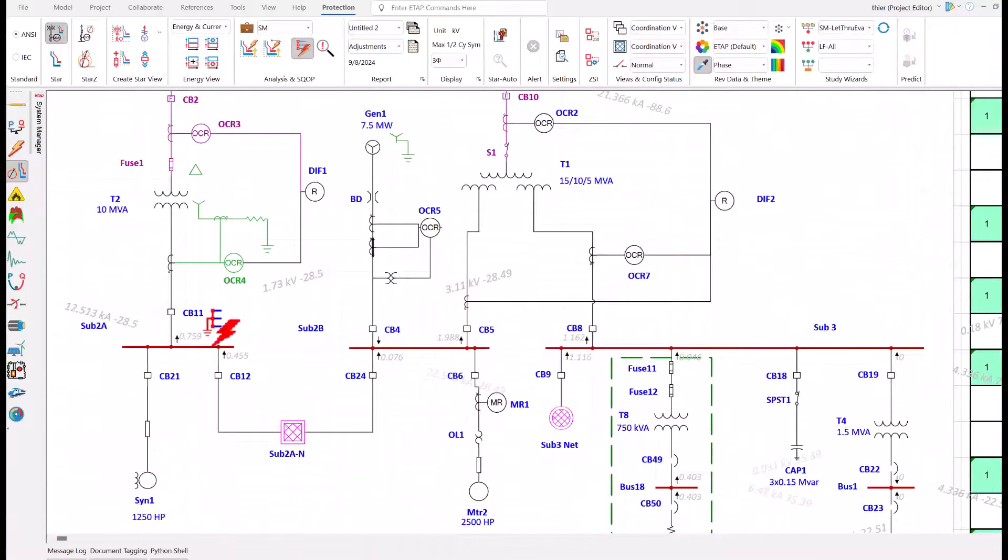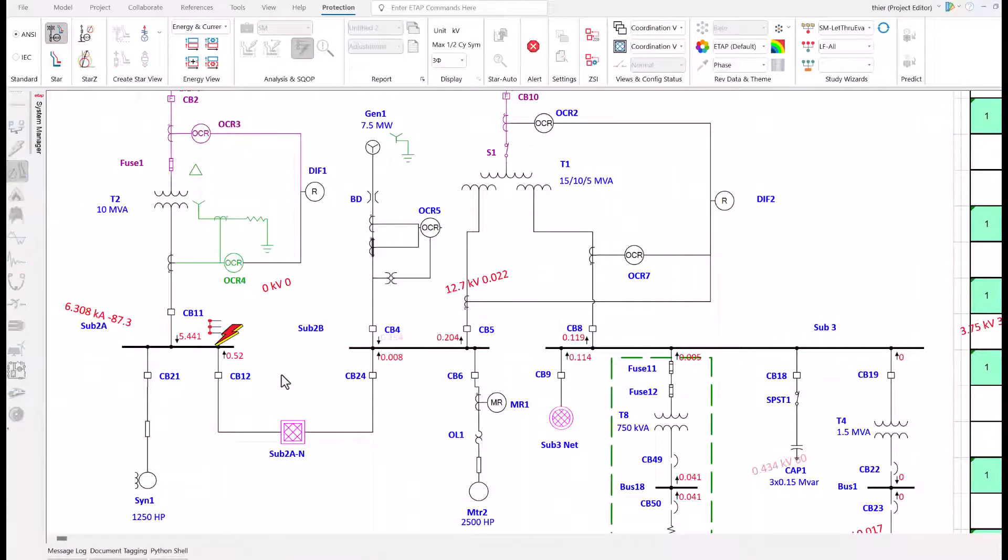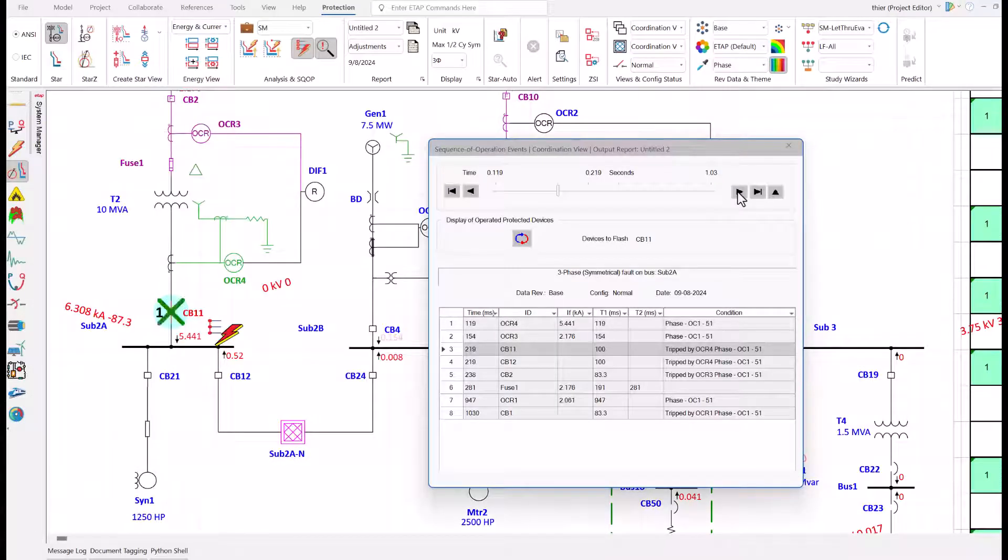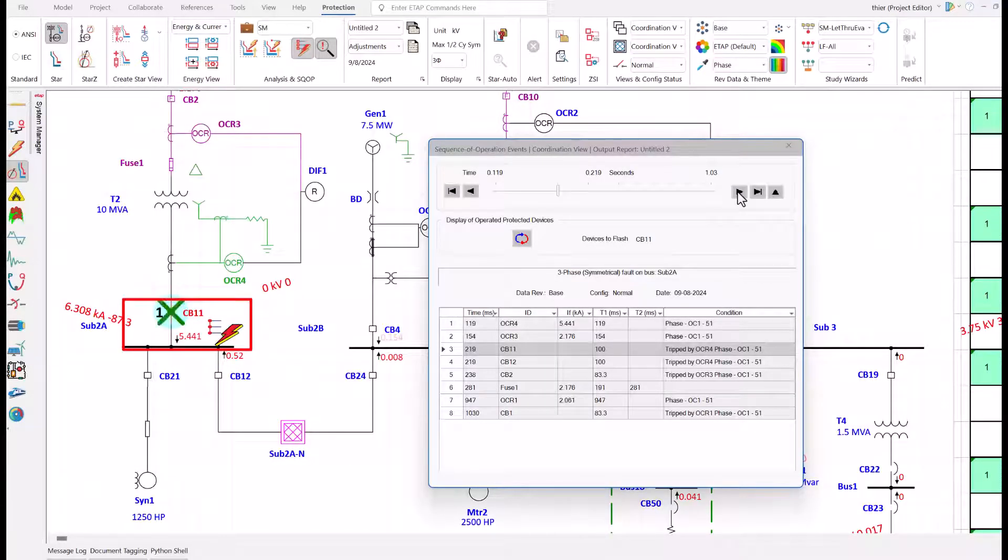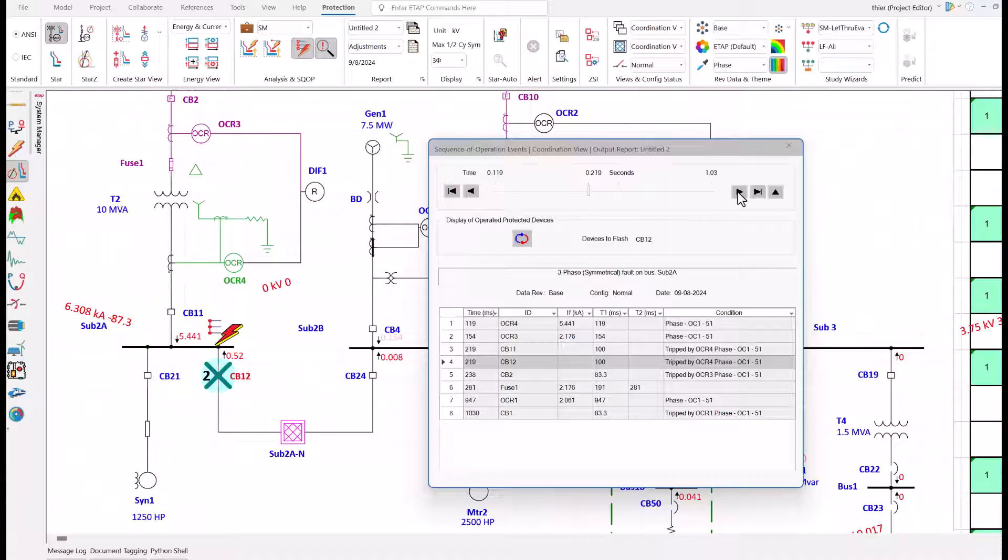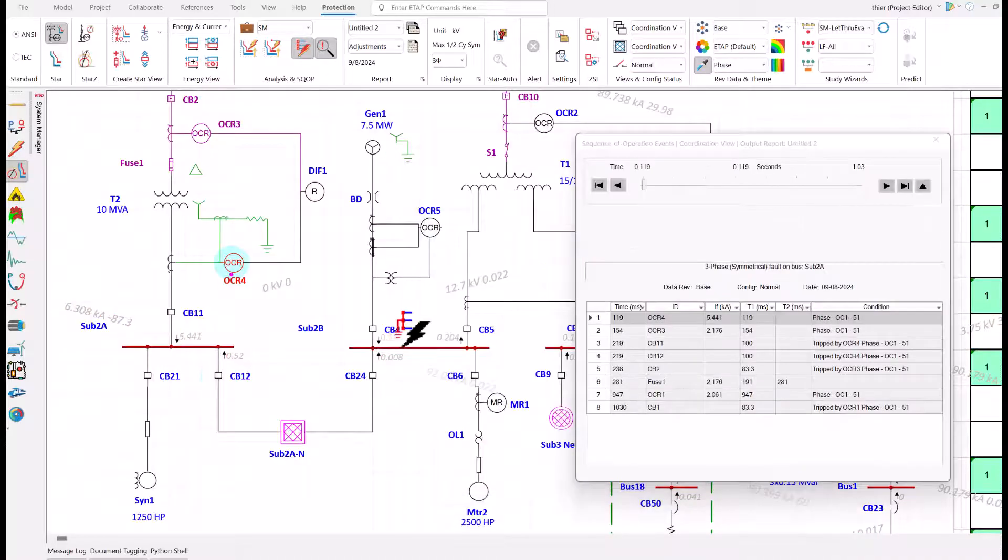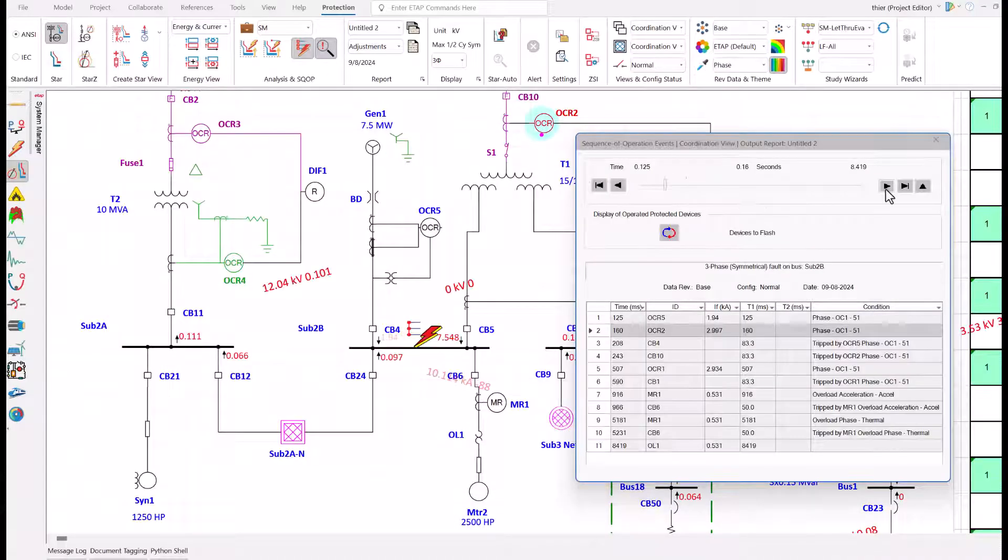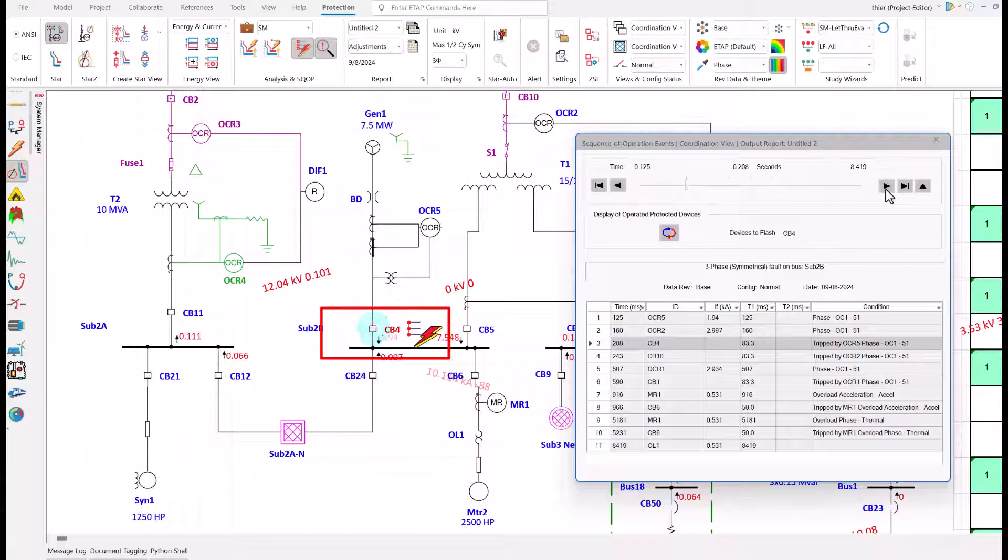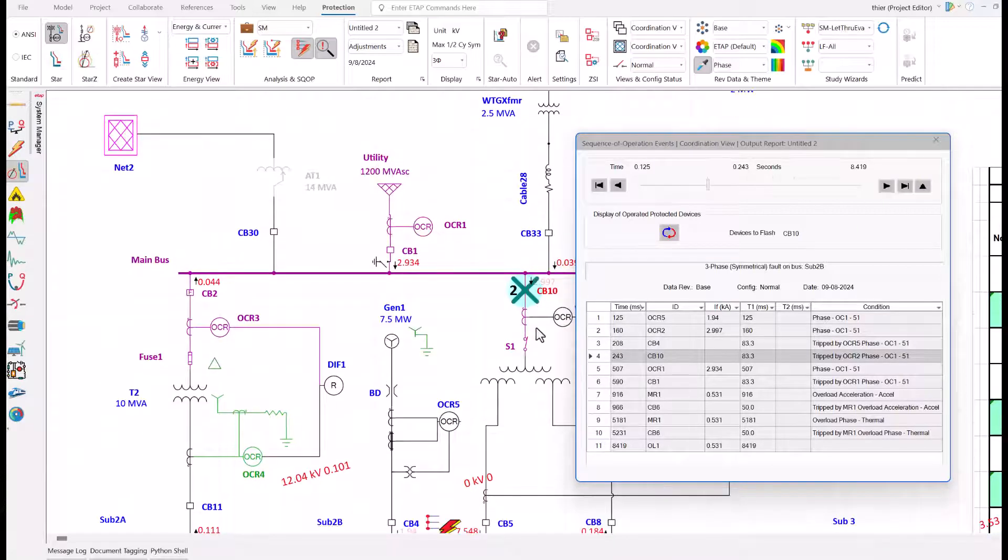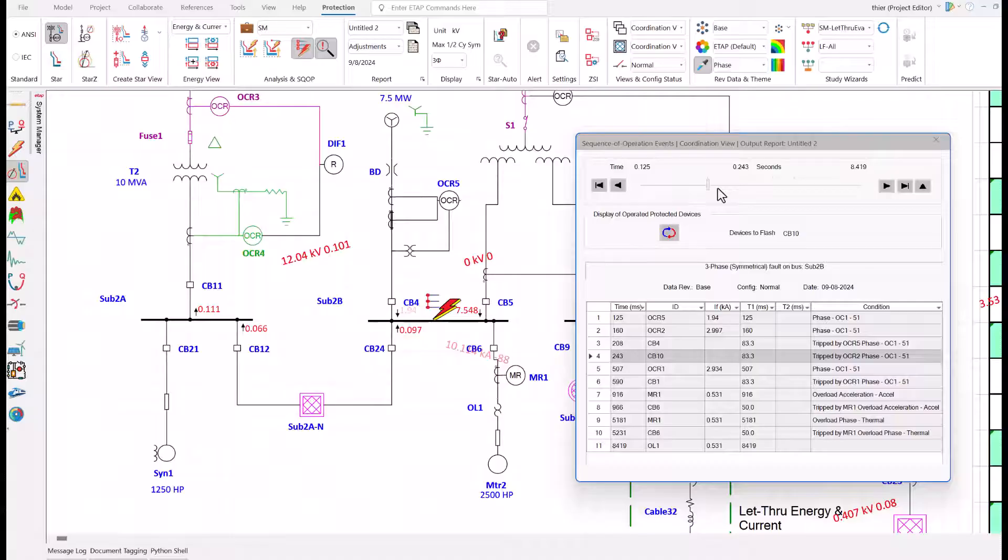There is a fault at sub 2A. We have CB11 which opens first - this is good coordination. CB12 also opens at the same time, which is great coordination. Fault at sub 2B: CB4 opens. Great coordination. We also have CB10 which opens at the same time. Perfect.